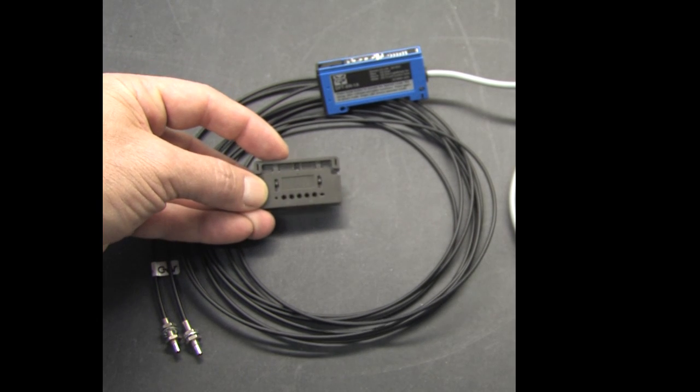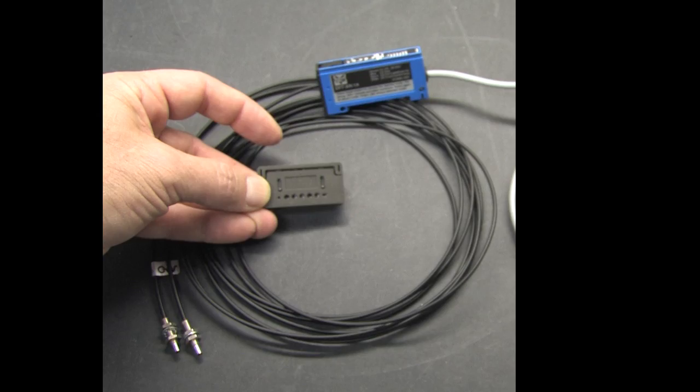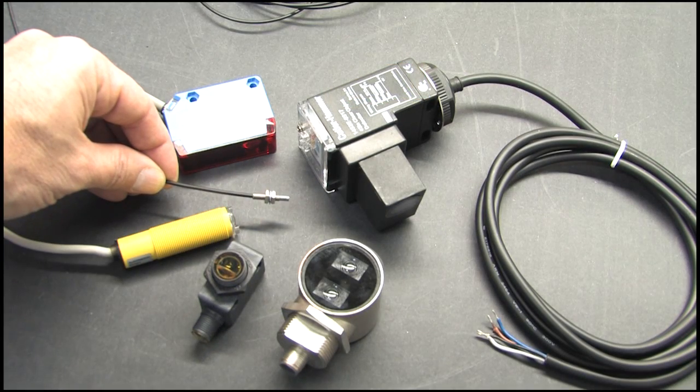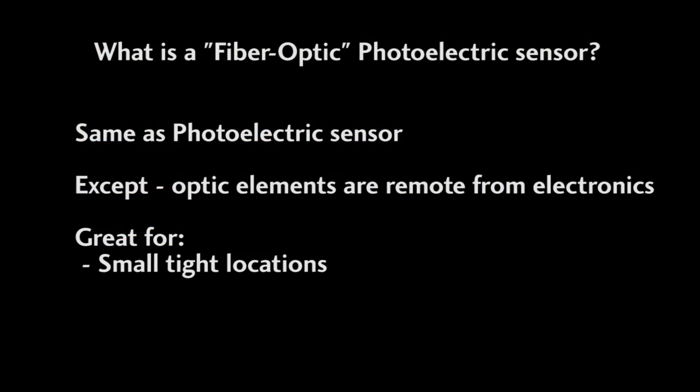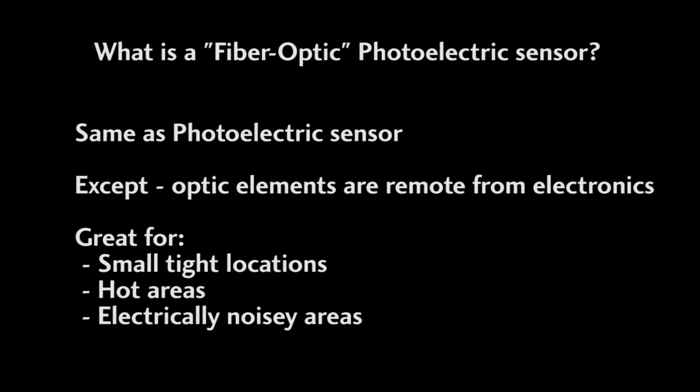These sensors even come with a special tool for cutting the fiber optic cables. You can get a feel for just how small these things are when I hold them right next to the regular photoelectric sensors. As you can see, these are great for squeezing into small tight installations where you can't fit traditional sensors. They are also great when you have an environment that might mess with the electronics like high heat or electronic interference, because with these you can put the electronics out of the way and only expose these passive optics to the hostile environment.